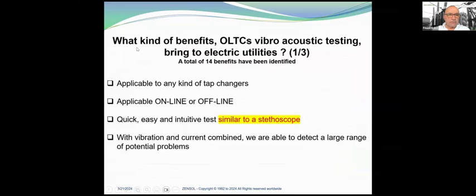What kind of benefits does OLTC vibroacoustic testing bring to electric utilities? A total of 14 benefits have been identified. First of all, it is applicable to any kind of tap changer, applicable online or offline, and the tests are quick, easy, and intuitive, exactly similar to a stethoscope. With vibration and current combined, we are able to detect a large range of potential problems.